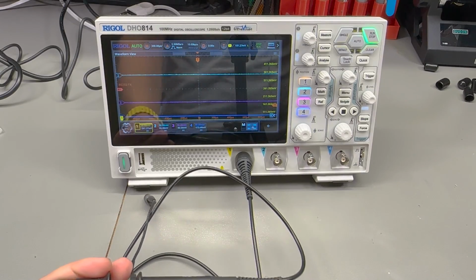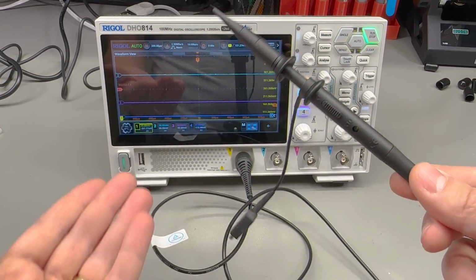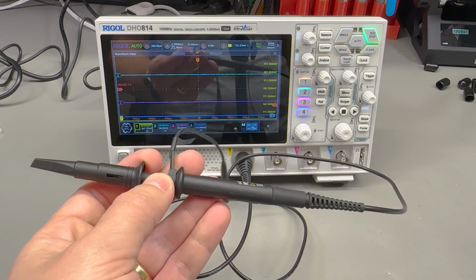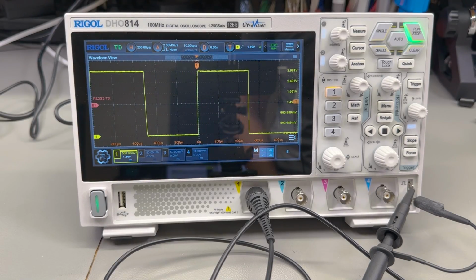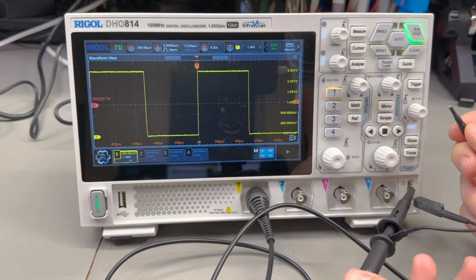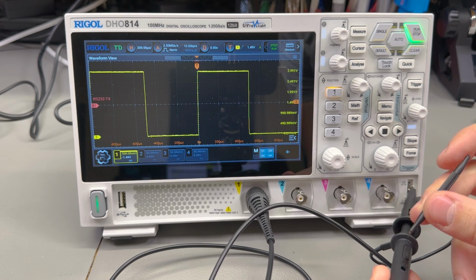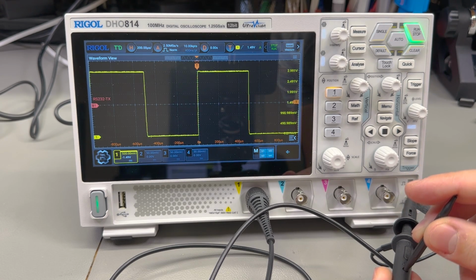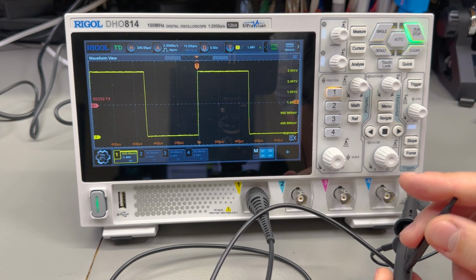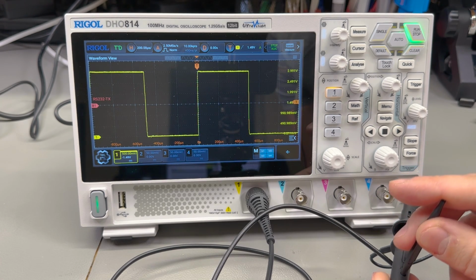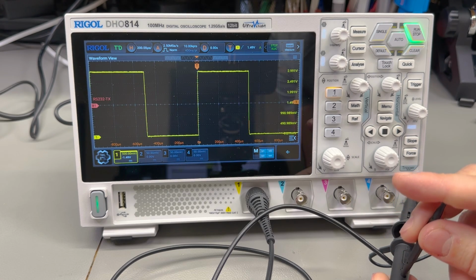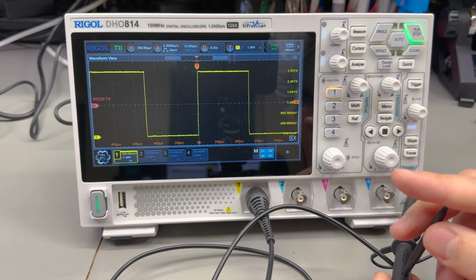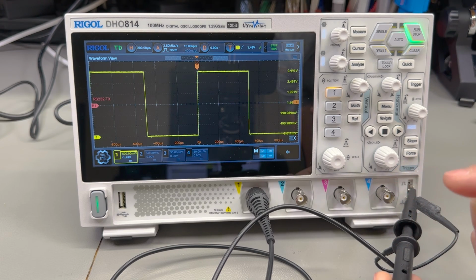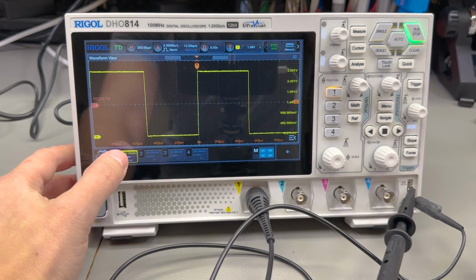And the first thing that you should do when you get a new oscilloscope or a new set of probes is to compensate them, because they might not be measuring correctly unless properly compensated. It's fairly easy to do that. You just have to hook up the probe to the test signal on the oscilloscope, which is a square wave, and then you go on the small compensation knob with the included plastic tiny adjustment tool, and you rotate that potentiometer until you see the best looking square wave with good rise and falling times on screen. To be honest, on this particular model, it doesn't really make a huge change when rotating that knob, so it will probably be fine even without calibration.